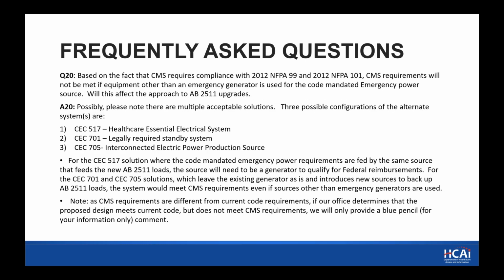And this is the last one. Based on the fact that CMS requires compliance with 2012 NFPA 99 and 2012 NFPA 101, CMS requirements will not be met if equipment other than the emergency generator is used for the code mandated emergency power source. That is a fact. Will this affect the approach to the AB 2511 upgrades? The answer is possibly. There are multiple acceptable solutions.